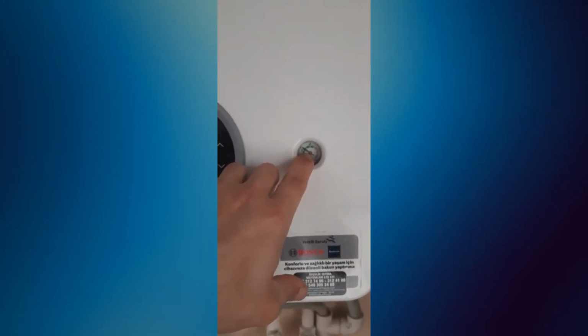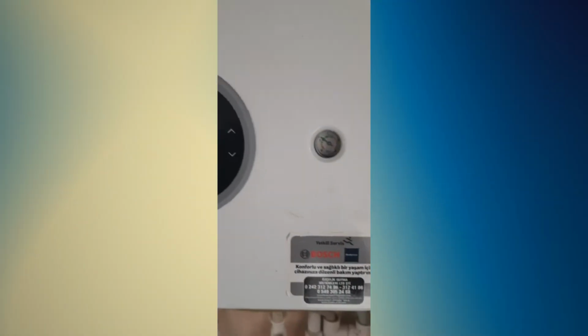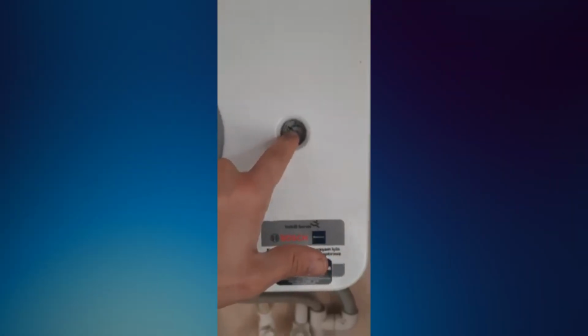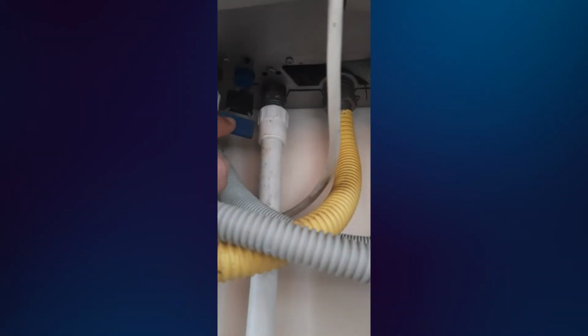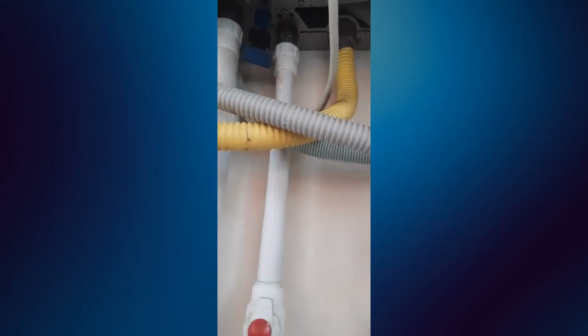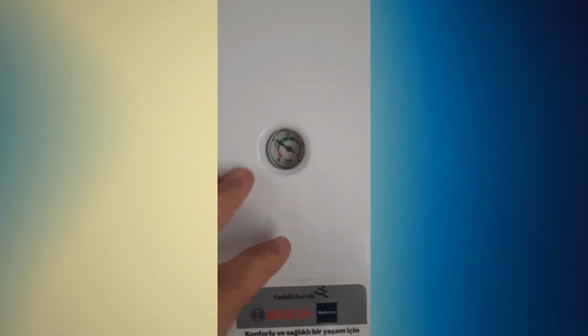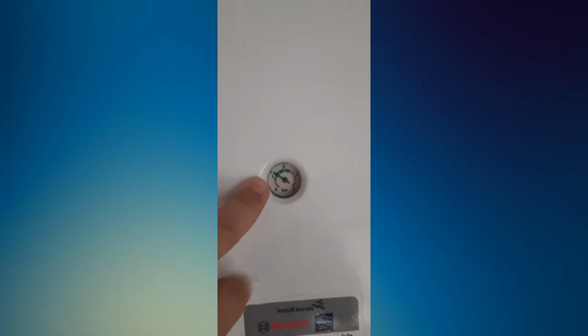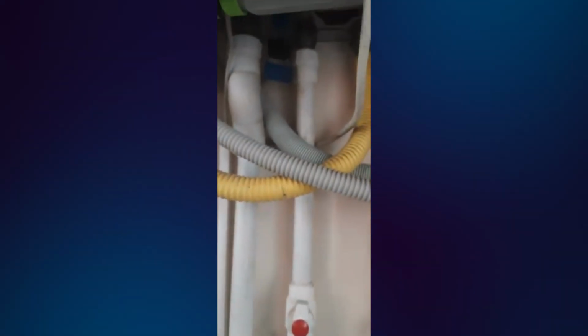Now, let's put this into a safe troubleshooting order. First, check whether there is any smell of gas. If there is, stop and call the emergency gas service. Second, check the boiler pressure. If it is too low, top it up according to the manual, usually to around 1 to 1.5 bar when cold. Third, check whether other gas appliances are working. Fourth, check whether the external condensate pipe is frozen or visibly blocked. Fifth, visually check the outside flue terminal for obvious obstruction, but do not dismantle it. Sixth, reset the boiler once after the basic checks. Seventh, observe what happens. Does the boiler ignite? Does it try several times and fail? Does hot water work but heating fail? Does the fault return immediately or only after a few minutes? That information is useful for the engineer.